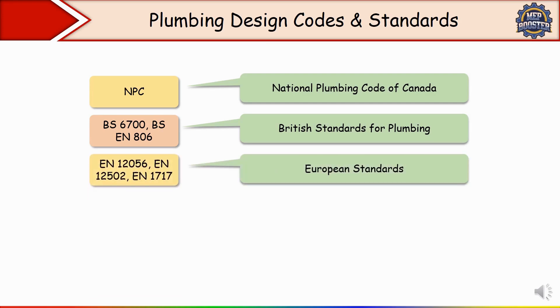Next we have European Standards — EN 12056, EN 12502 and EN 1717 — published by the European Committee for Standardization and used across Europe, providing regulations for water supply and drainage systems. EN 12056 covers gravity drainage system design, EN 12502 covers corrosion protection for plumbing pipes, and EN 1717 covers protection against backflow contamination. For example, in Germany, EN 1717 is followed to install backflow prevention devices in commercial kitchens to prevent contamination of drinking water.